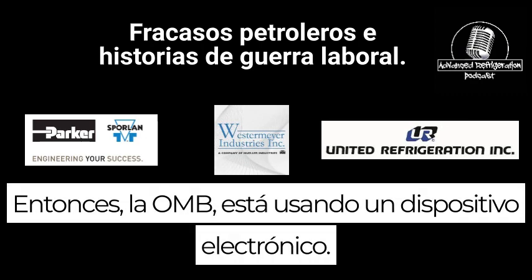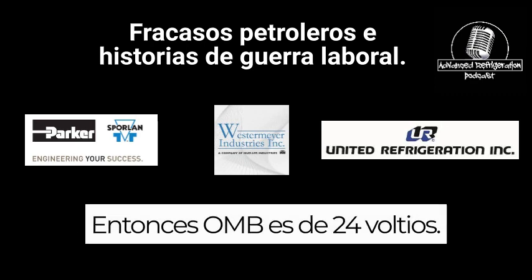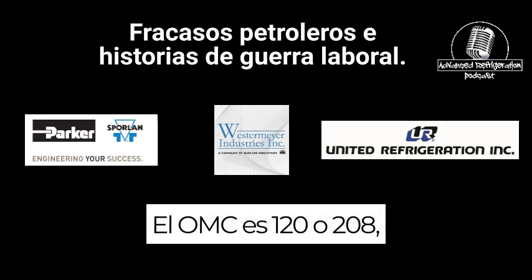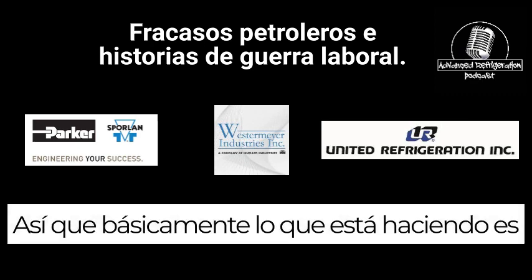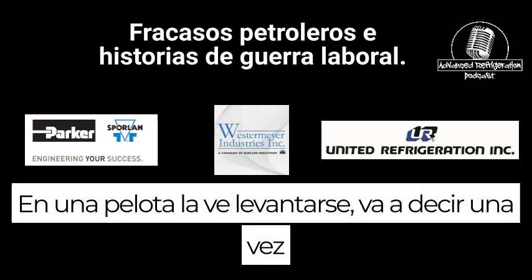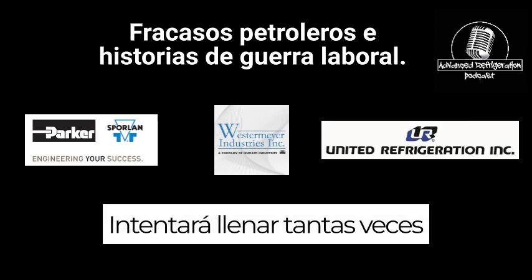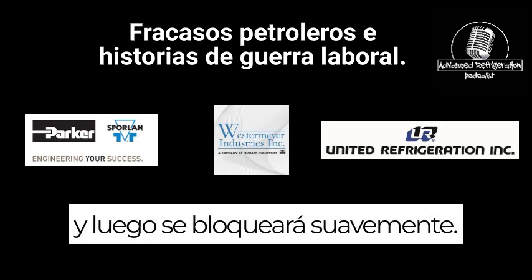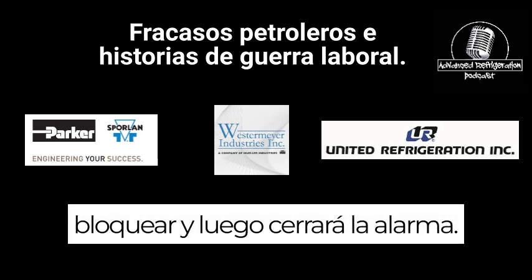Okay, so with the OMB, you're using an electronic oil float, and a couple things with this. The OMB is 24 volts. The OMC is either 120 or 208, depending on which one you have. Basically, it has a float inside the compressor in a ball. Once it sees the level drop down, it's going to start to fill. It'll attempt to fill so many times, and then it'll soft lock out. And after it soft locks out several times, then it'll hard lock out, and then it'll close the alarm.